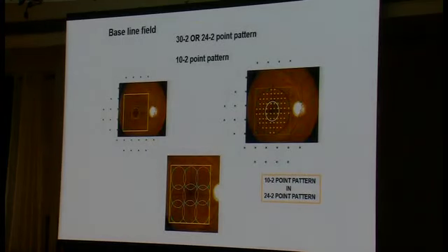The most important factor is that we talk a lot about the bare area around the center, but in 24-2 or 30-2, within the 10-degree circle there are only 16 points and there is a huge bare area. If any scotoma starts at this point, it is likely to be missed. It will be picked up in 10-2 because this bare area is filled with points, where the distance from point to point is 2 degrees.